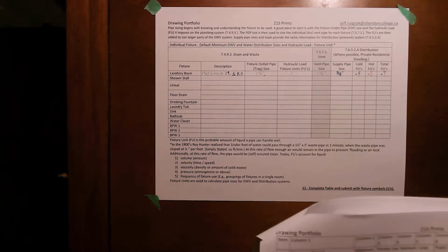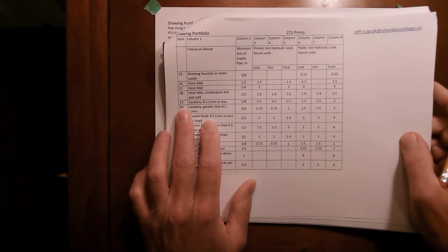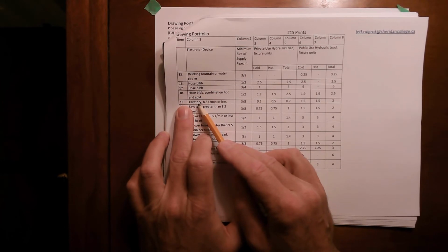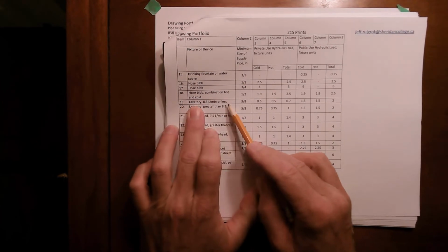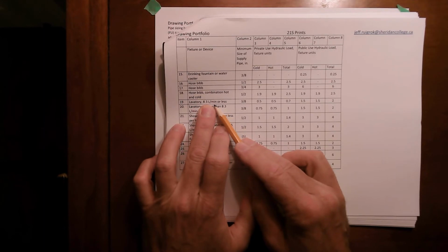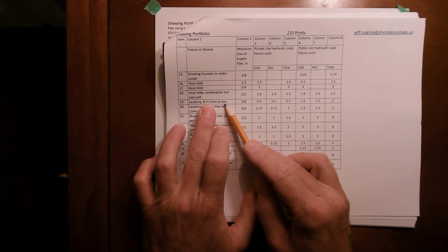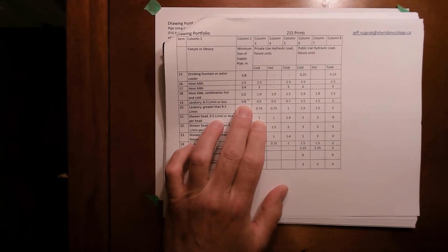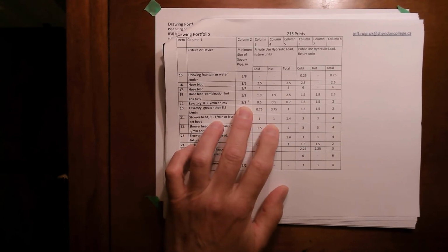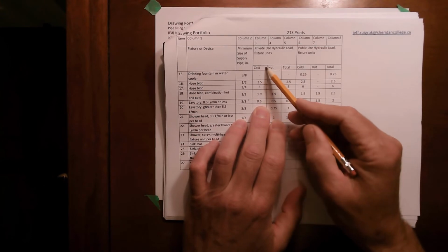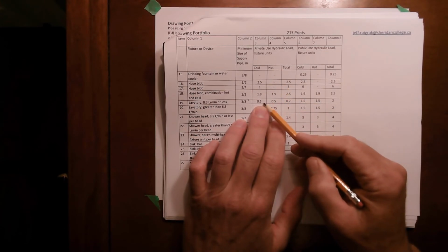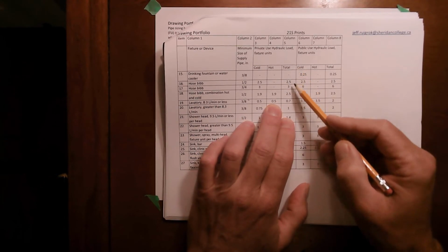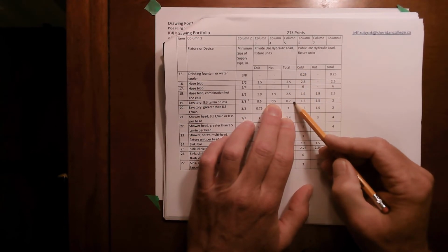Yeah, so let's look at that table then. So here we are here, 7632A, number 19, lavatory basin, 8.3 liters per minute or less, 3/8 pipe size. And then you got a cold load, 0.5, a hot load of 0.5, and a total load of 0.7.